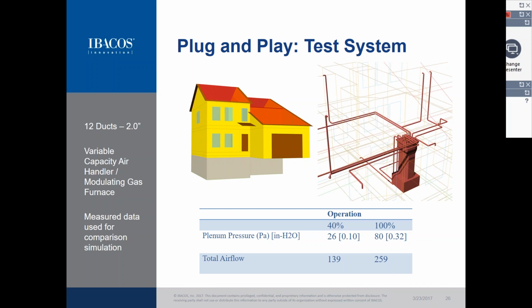Another little interesting tidbit of data to point out is that static pressure was a primary concern using these smaller diameter ducts. And with the system that was installed in the lab house, again with these 12 2-inch ducts, we were able to deliver 260 CFM with only 0.32 inches of static at the plenum. So that's the amount of static that was available to the duct system. This system had a very minimal return, and so that certainly helps in being able to minimize the total external static pressure so that the majority of that pressure is available to the duct system. But again, we saw a lot of promising results here, both from a comfort performance and from an air delivery performance.